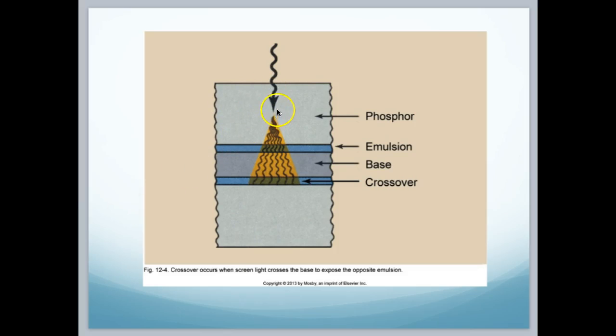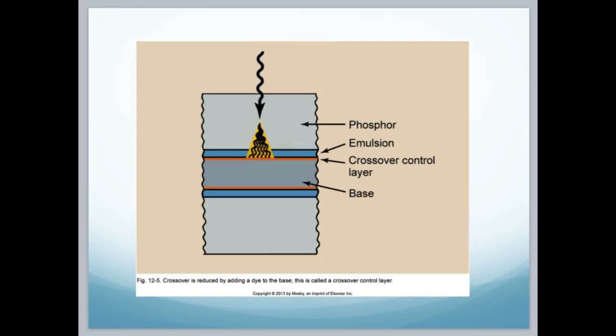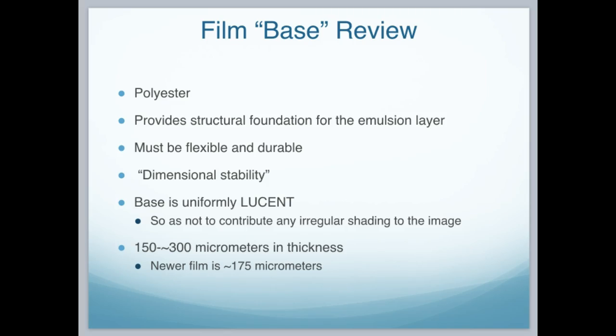We have a phosphor here with photons coming in, making a glow. If we didn't have a base that would stop that, the glow would cross over to the other phosphor and expose it differently — that image would be more magnified than this one. With the tint in the base layer, it's considered the crossover control layer, because it doesn't allow the phosphorescence of one side of the film to cross over to the other side. The film base is composed of polyester, giving it a good structural foundation for the emulsion layer. It must be flexible and durable, shouldn't shrink, keeping its dimensional stability. The base is uniformly lucent, 150 to 300 micrometers in thickness, and newer films are about 175 micrometers.